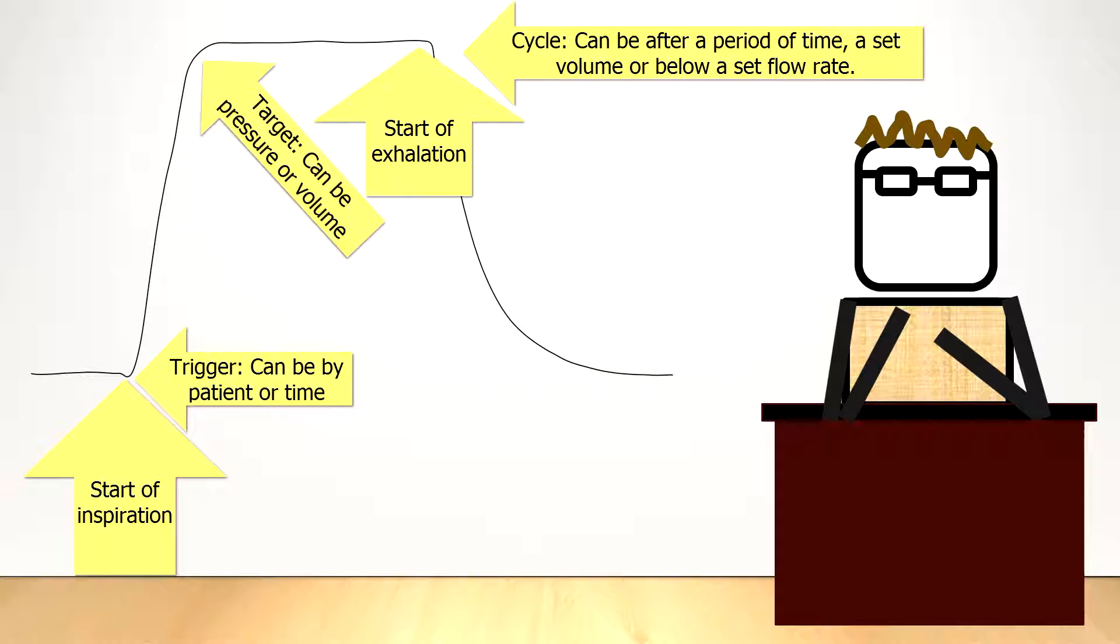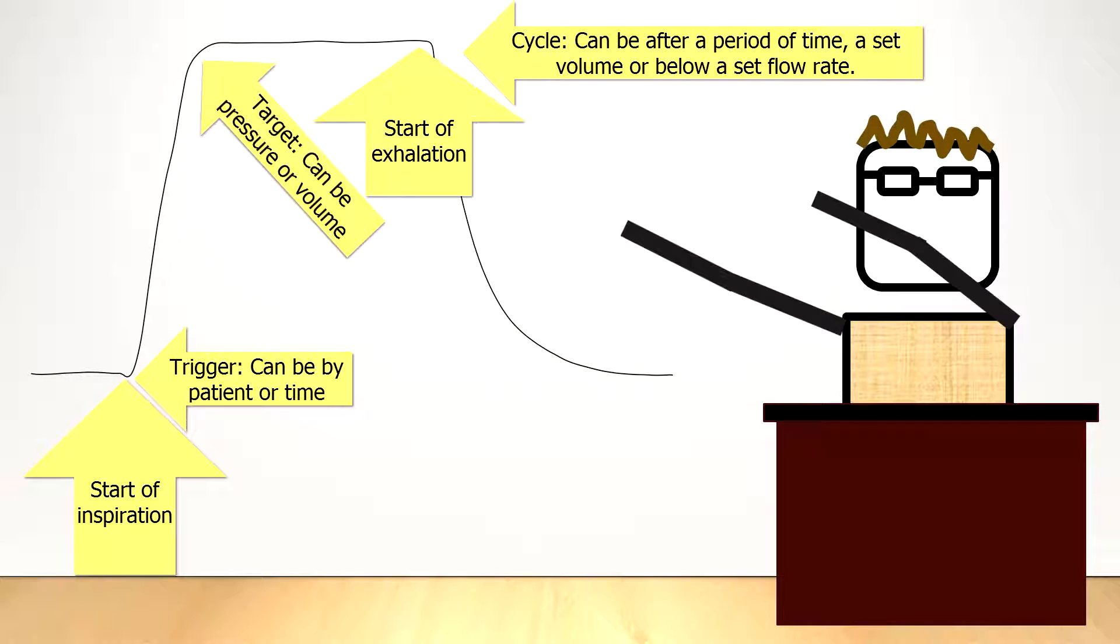Exhalation itself is passive and is not a controlled variable. One thing to watch when you're ventilating a patient is to observe the flow pattern on the exhalation limb to ensure that a complete exhalation has occurred prior to the initiation of the next breath. If there is still flow present during exhalation just as the next breath is delivered, then this means that gas trapping is occurring.